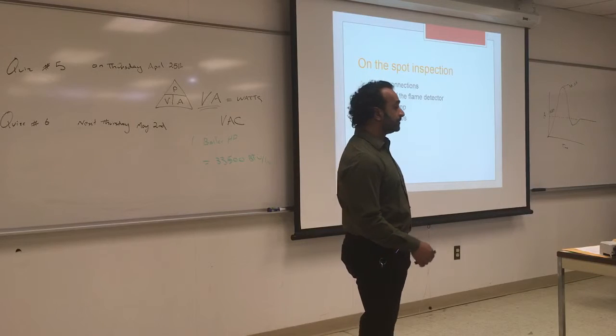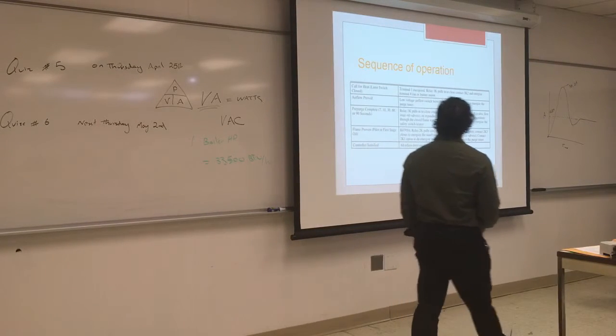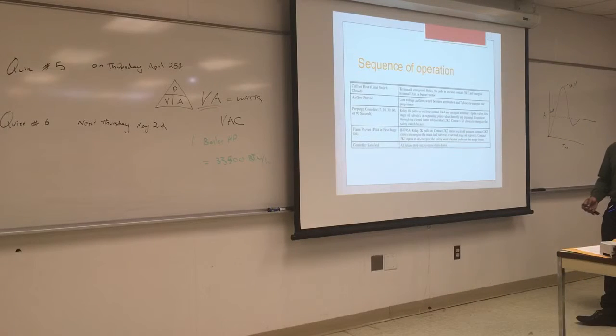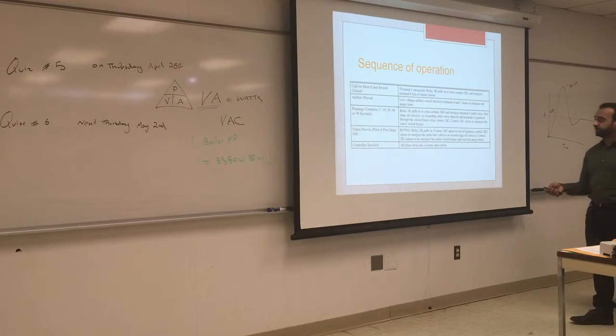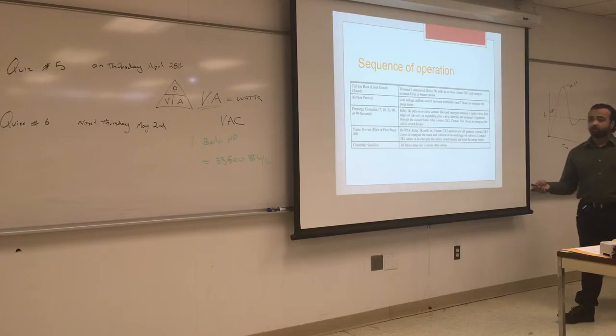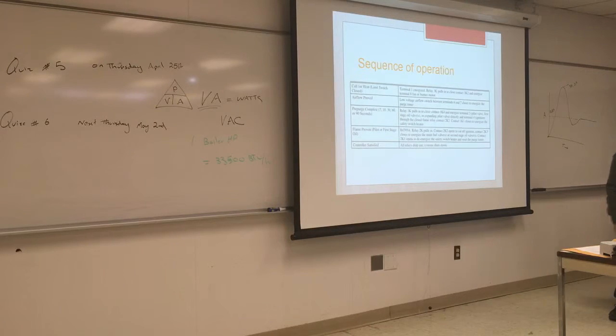Limit switches. Sequence of operation. So first we have the call for heat. That's very similar to what we have for residential. Terminal 1 will energize, relay 3 will pulse in and engage contact 3K2 and energize terminal 8 for the fan or burner motor. So that's the pre-purge process. Airflow is proved after the airflow switch has proved that it's running. It will turn on the next stage, which is the pre-purge complete, and then we light the pilot. Once the pilot is proven, the other relay will pull in, and the controller is satisfied, and the main flame is activated.